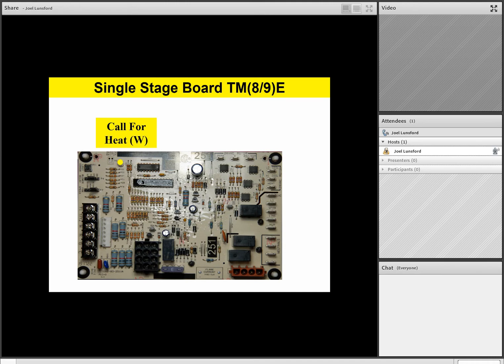Okay, and then as we take a look at this single stage board again, that's page number 21, we have a red LED in this example, and it's two red flashes. And so as you take a look at page number 21 for our single stage board again, it's a 2 red flash LED. And let's please check the following. In this example, we have a pressure switch that's closed. Now, the pressure switch itself might be stuck closed for some reason. If it is, then you replace the switch.